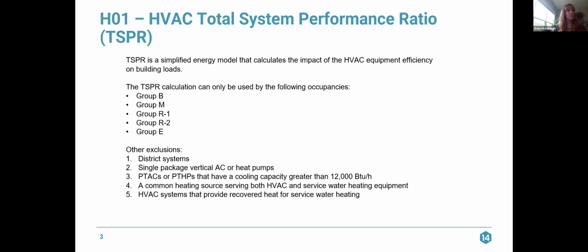It's a simplified energy model that calculates the impact of HVAC equipment efficiency on building loads. There are a lot of barriers to who can use the TSPR method. The only group occupancy types that can use the method are Group B, Group M, Groups R1 and R2, and Group E. There are other exclusions if you're using district systems, so district cooling, district chilled water, district hot water, district steam. If you have single package vertical air conditioners or heat pumps, you cannot use it.